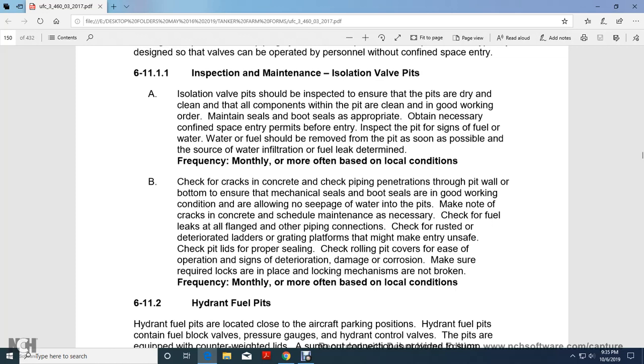Check for cracks in the concrete. Check the piping penetrations. Check the pit wall and the bottom. Ensure the mechanical seal of the boot seal is in good working condition and allowing no seepage of water into the pit. Make note of cracks in the concrete. Schedule maintenance if necessary. Check for fuel leaks at all flanges and other piping connections. Check for rusted, deteriorated ladders and grating platforms that make the entry unsafe.